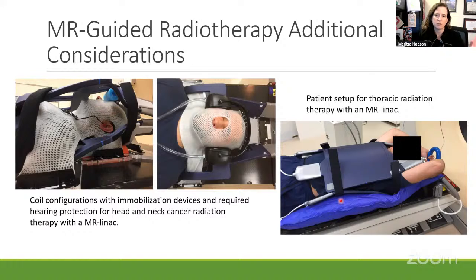Okay, these are two examples of coil configurations with MR-guided radiotherapy patients. On the right is the patient setup where the posterior coil is actually right underneath the patient here, and then there's the back lock. And then you have the anterior coil here placed on top of them. And they're strapped together with Velcro. We do this to minimize the distance between the coils, so that increases your signal to noise ratio, because there's no coil built into the table for these systems like you would see on an MR simulator or just a straight up MRI.